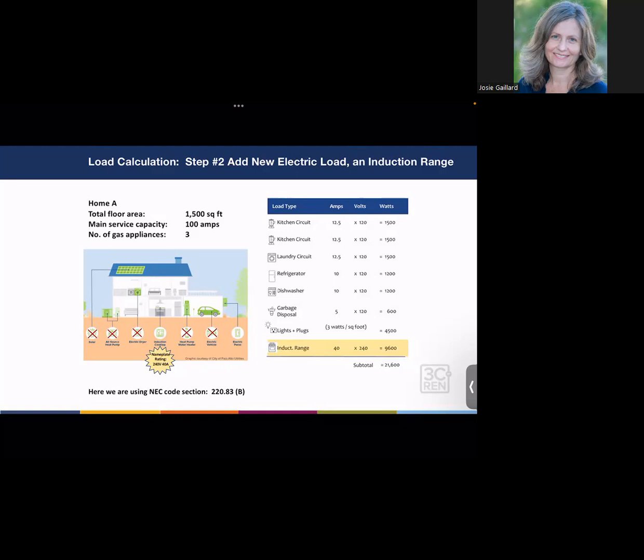How do we know about the lights and plugs? This is an assumption based on the square footage of the home. We know the home has 1,500 square feet, and the code tells us to assume 3 watts per square foot. So we multiply 3 times 1,500 square feet and get 4,500 watts assumed for all the light and plug loads throughout the home.